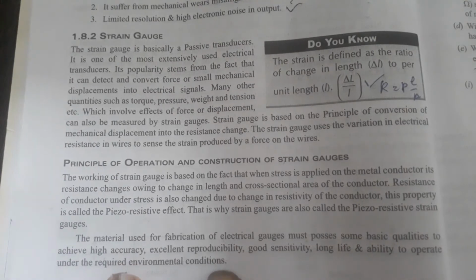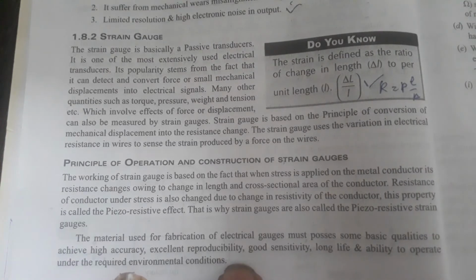Now I will discuss the principle of operation and construction of the strain gauge. The working of the strain gauge is based on the fact that when stress is applied on a metal conductor, the resistance changes owing to change in the length and cross-section area of the conductor. Resistance of the conductor under stress also changes due to the change in resistivity of the conductor. This property is called the piezoresistive effect.